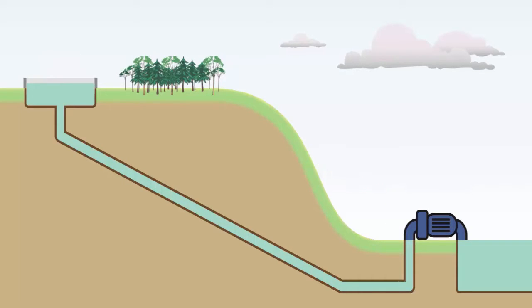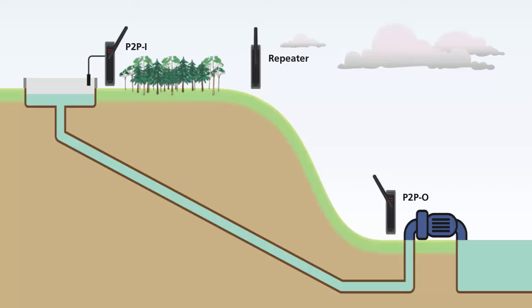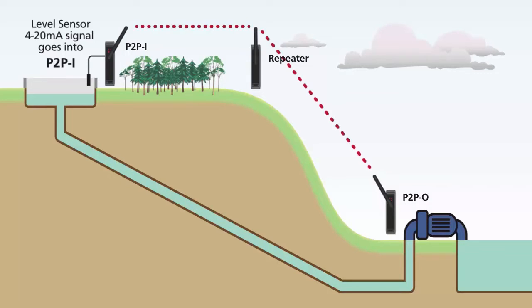To achieve a successful link, 3 devices are required: the TwinLink I/O pair plus a repeater unit. The P2P-I unit measures the 4 to 20 mA output signal from the reservoir level sensor. This signal is converted to a digital message and transmitted to the repeater. The repeater forwards this digital message to the P2P-O unit. It reconstructs a signal into a 4 to 20 mA output that is wired to an existing pump controller.